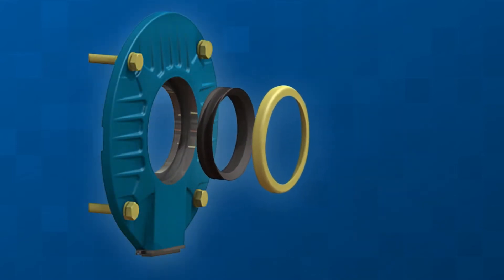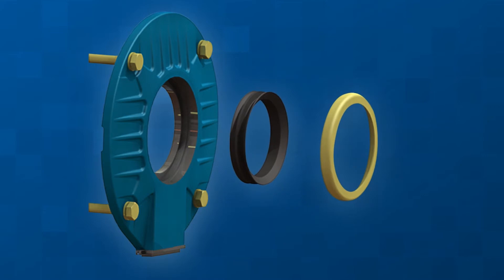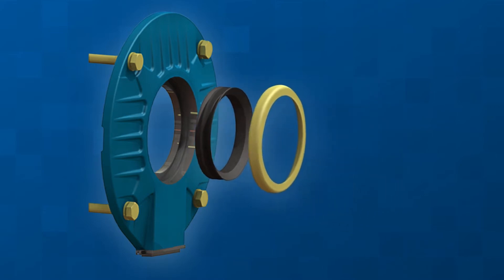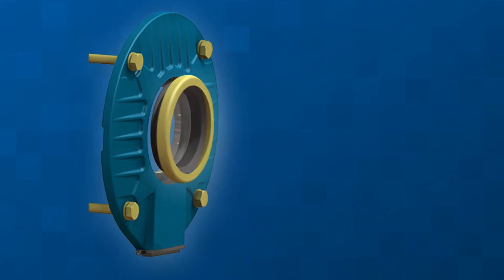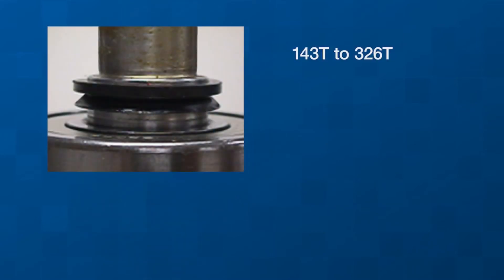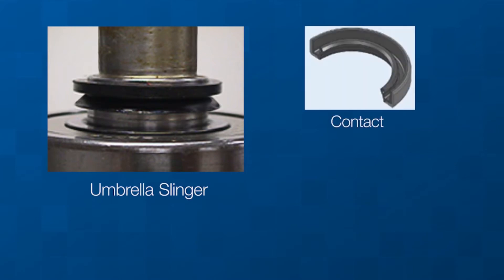On 364T and larger models, the exclusive WSeal sealing system, composed of a double lip V-ring and a metallic cap, protects against dust and liquids. For frame sizes 143T to 326T, the proven V-ring seal operating on a machined surface provides IP55 protection. Other available seal options, depending on frame size, are slinger, contact and labyrinth.